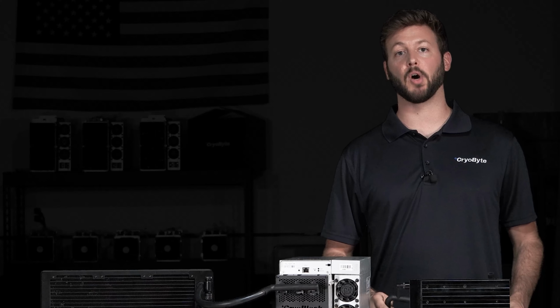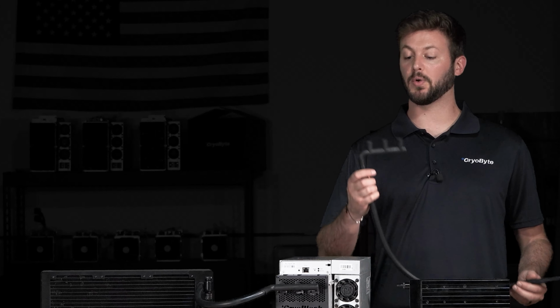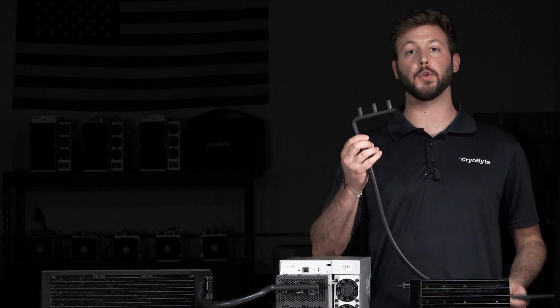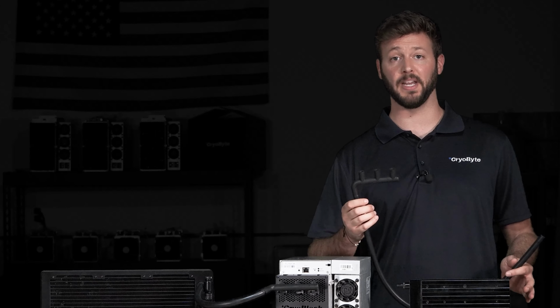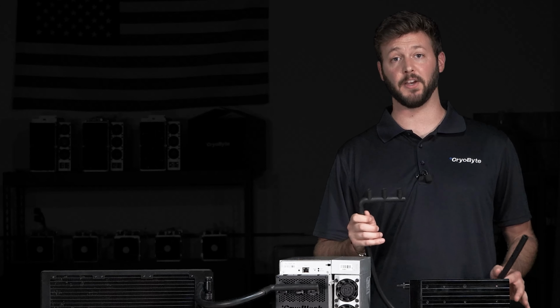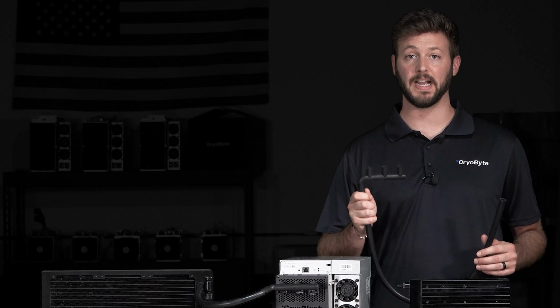By utilizing the barb and compression fitting, we're able to create a single piece manifold hose design using EPDM tubing. This eliminates a lot of the points of failure you see in traditional water-cooled miners.